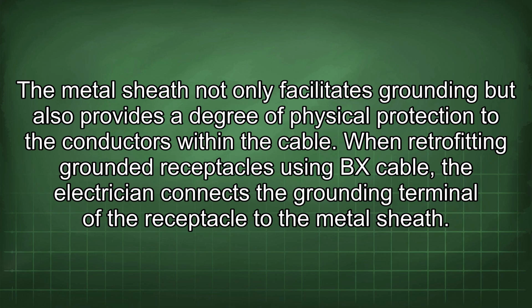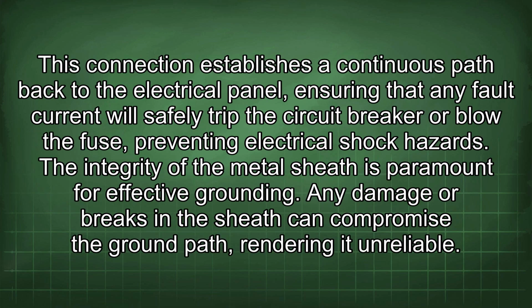conductors within the cable. When retrofitting grounded receptacles using BX cable, the electrician connects the grounding terminal of the receptacle to the metal sheath. This connection establishes a continuous path back to the electrical panel, ensuring that any fault current will safely trip the circuit breaker or blow the fuse, preventing electrical shock hazards.